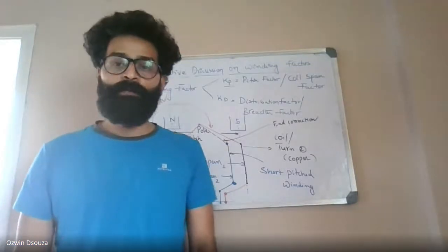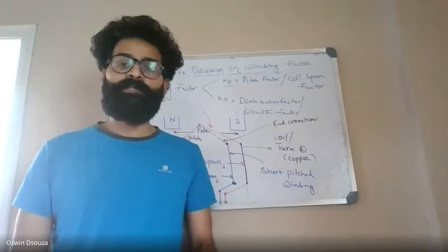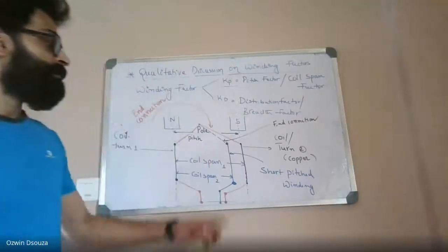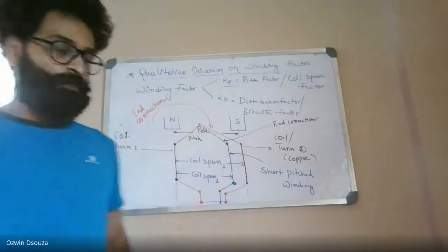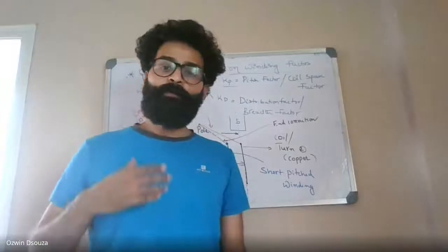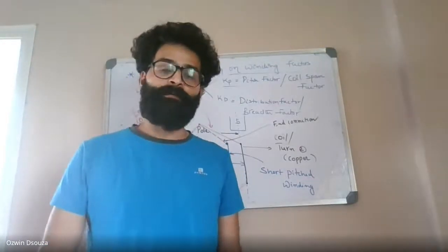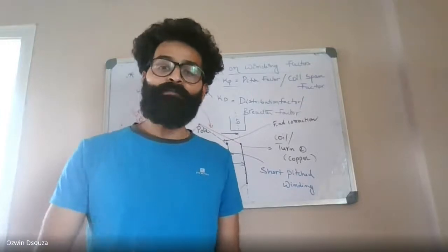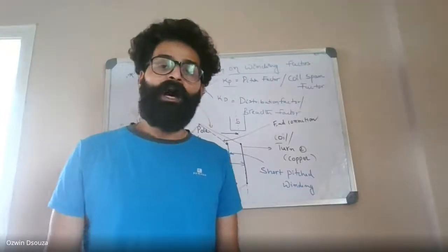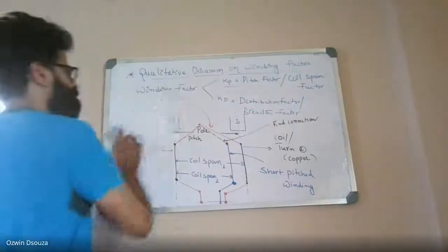By saving copper, we can achieve cost-effective machine design. The second advantage is that with the help of short pitched winding, the wave shape of the induced EMF remains almost sinusoidal. That means it also helps in eliminating so-called harmonics. So that's the advantage of a short pitched winding.